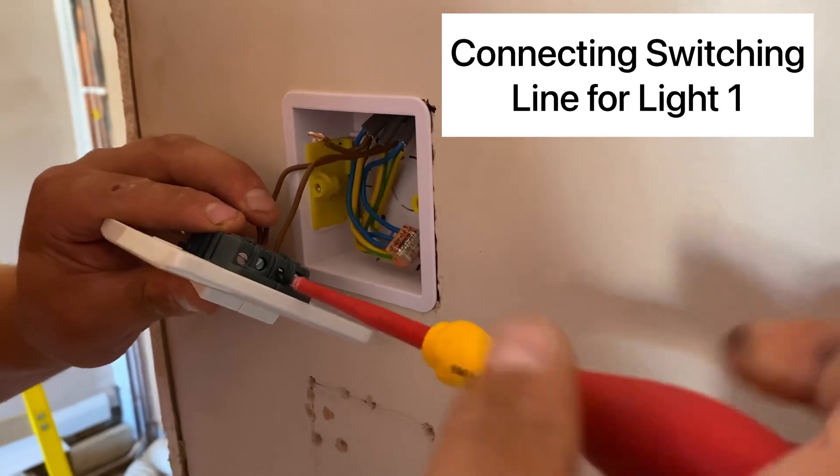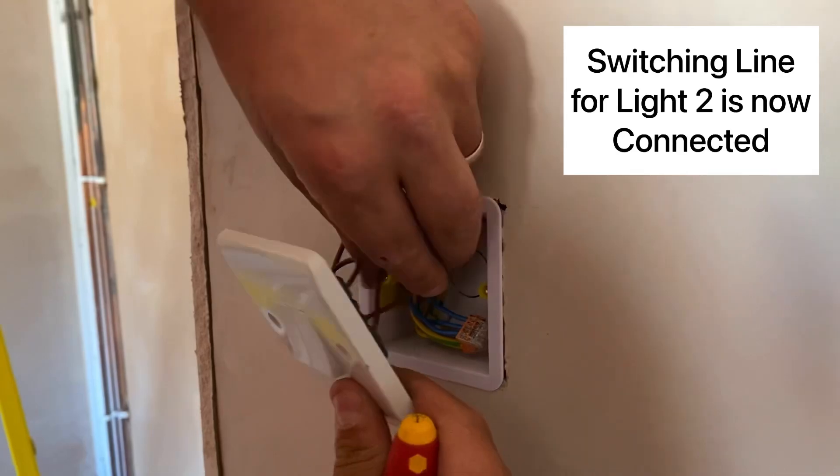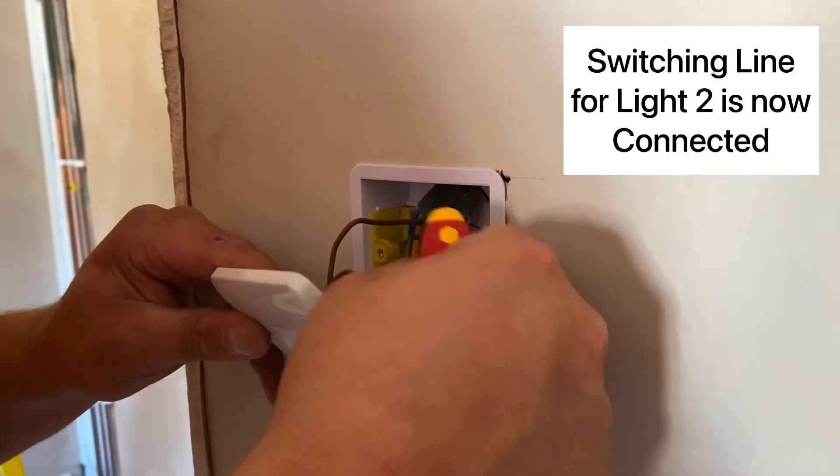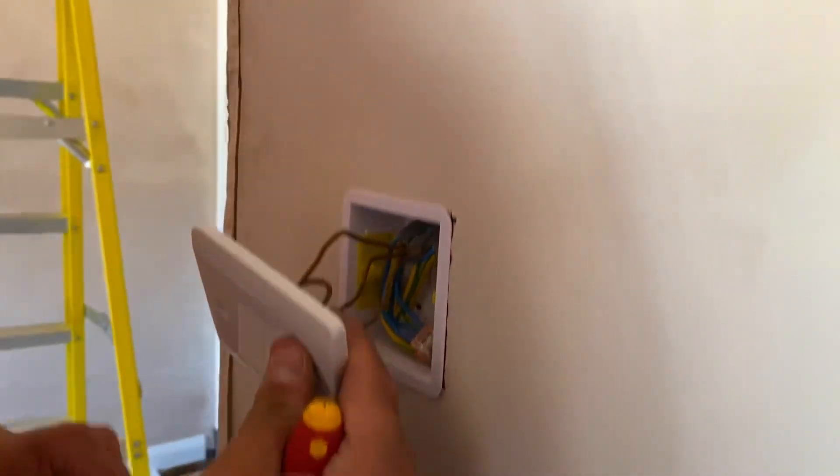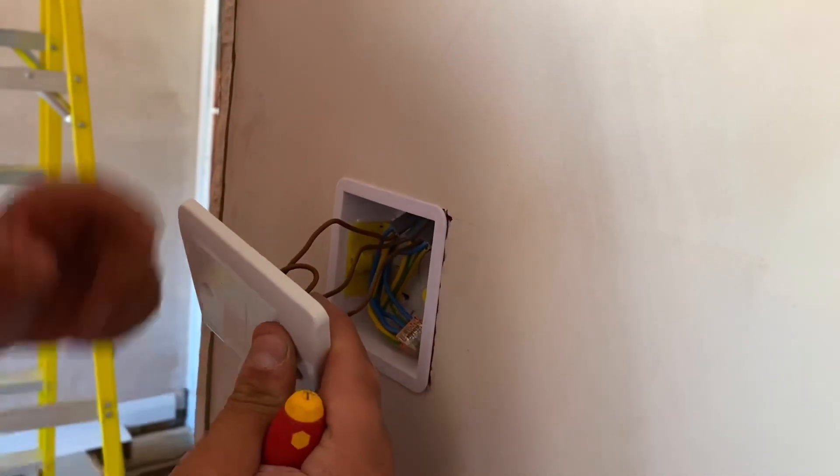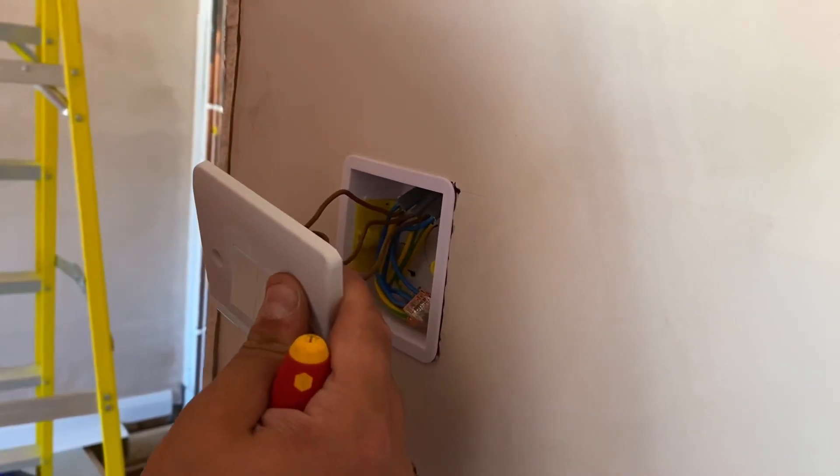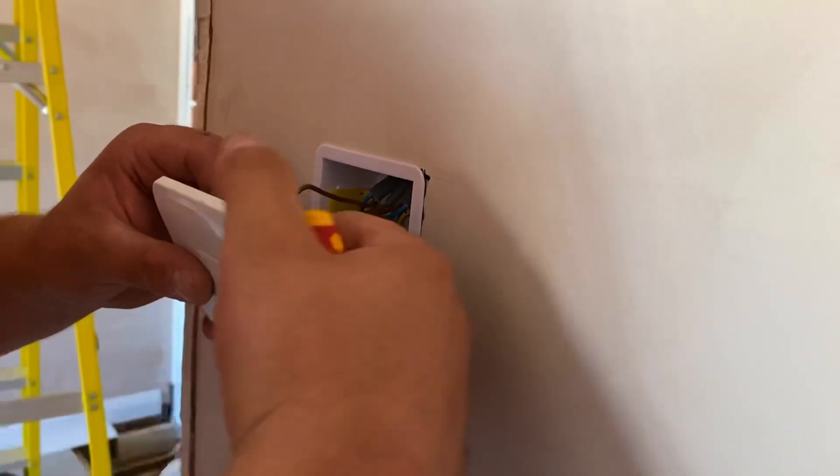Switching line, switching line, and then we have a permanent feed with our bridge connection across the two commons to give both sides a permanent feed. Now if you add a three gang switch again, you could bridge again and again and again until needed.